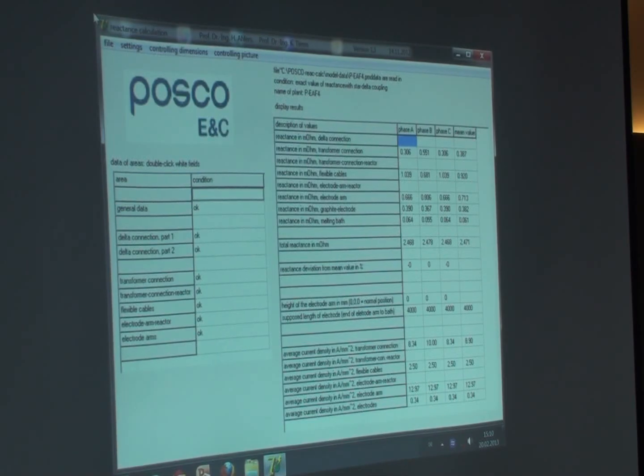This is the idea, but it is not so easy. Where can we measure? On the primary side of the furnace transformer, or on the high current side? To measure on the high current side is not easy because you cannot measure exactly the current. The most results are given on the primary side of the furnace transformer.